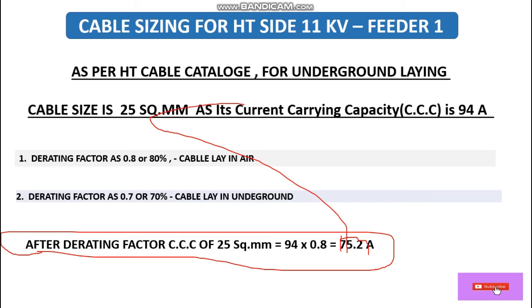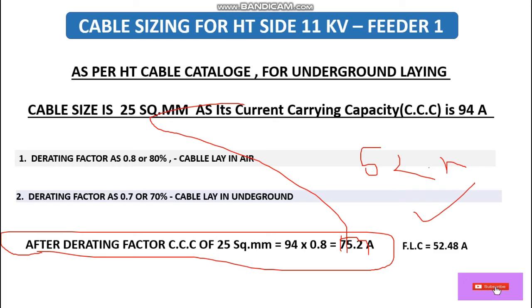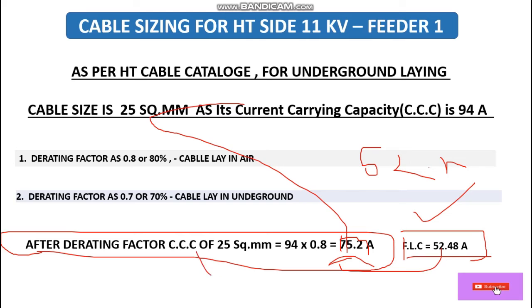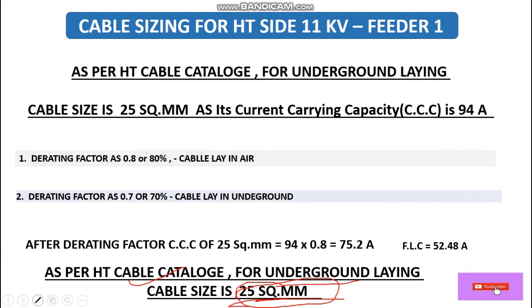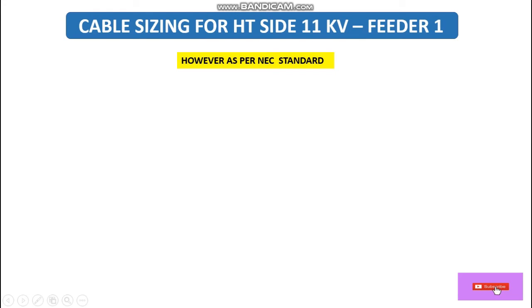After applying the derating factor, the current carrying capacity becomes 75.2 amperes. Our full load current is 52.48 A. Since 75.2 A is still greater than the full load current of 52.48 A, this 25 sq mm cable is sufficient based on current carrying capacity.